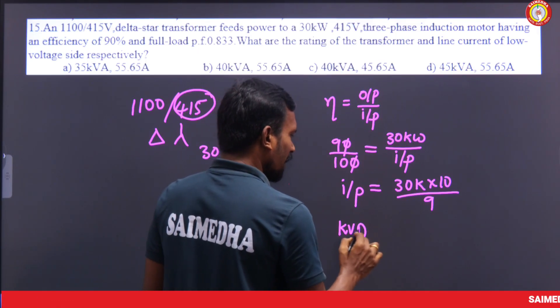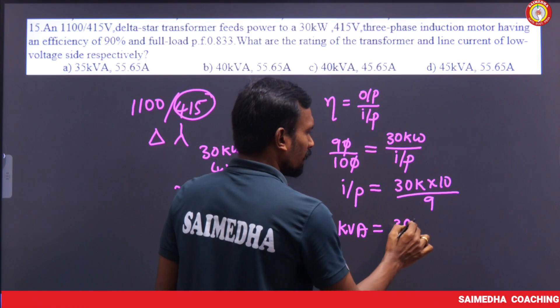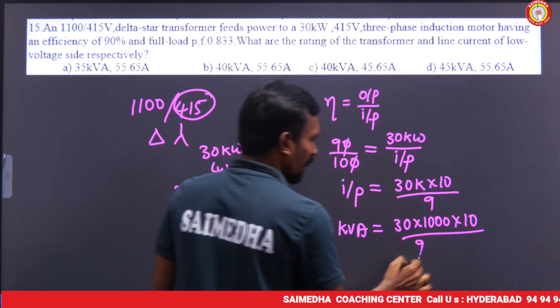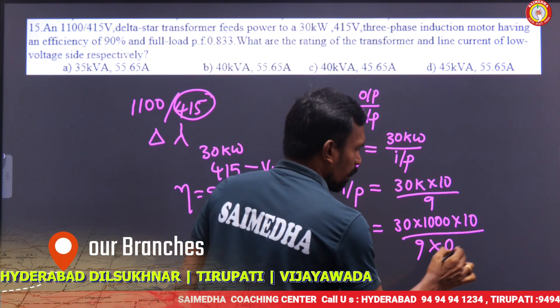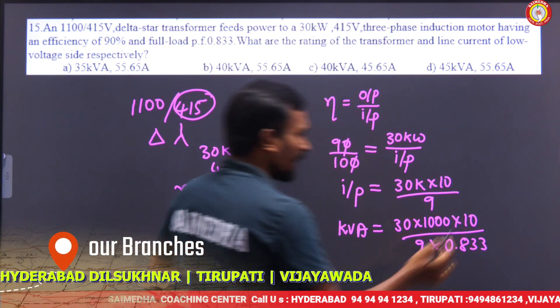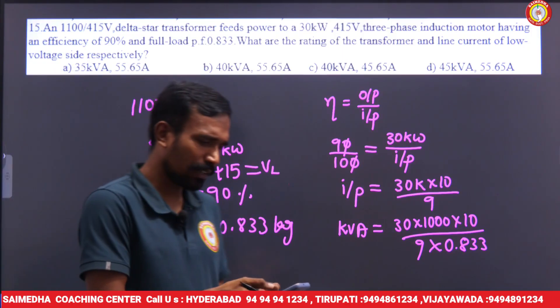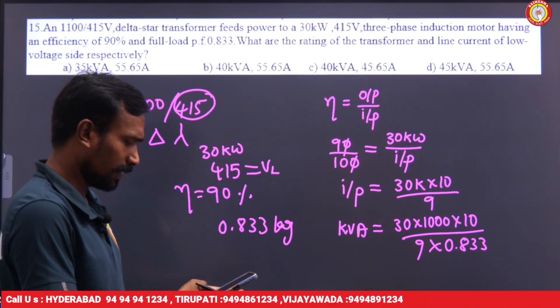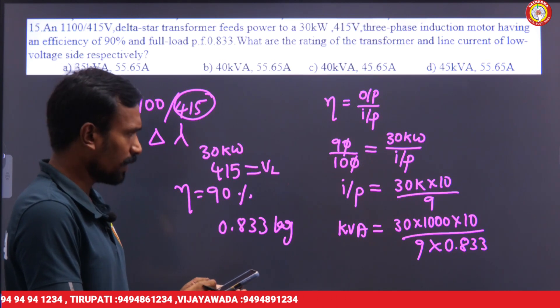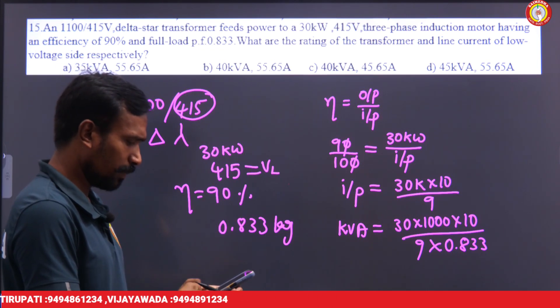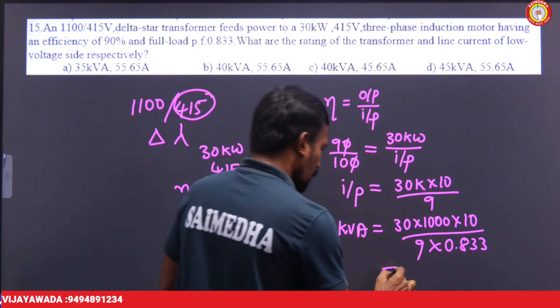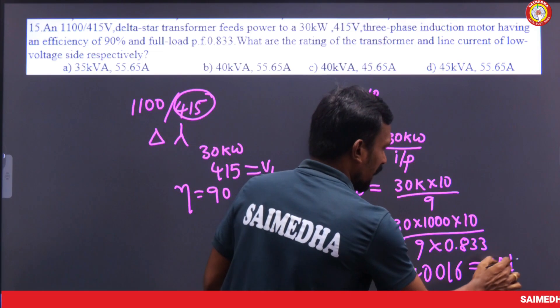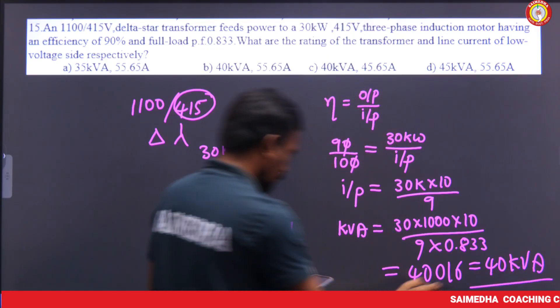KVA equals 30,000 into 10 divided by 9, then divided by the power factor 0.833. That gives 30,000 × 10 ÷ 9 ÷ 0.833, which is approximately 40,016 — which is nothing but 40 KVA. That is the transformer output.